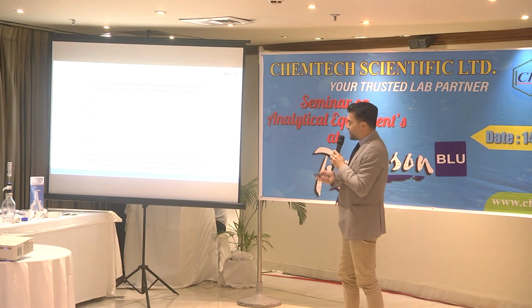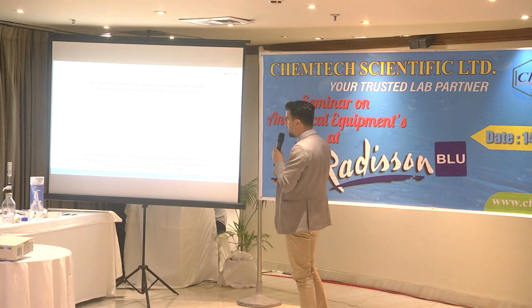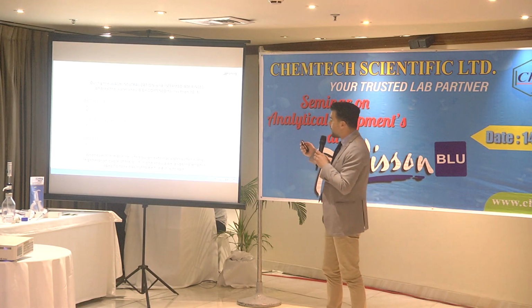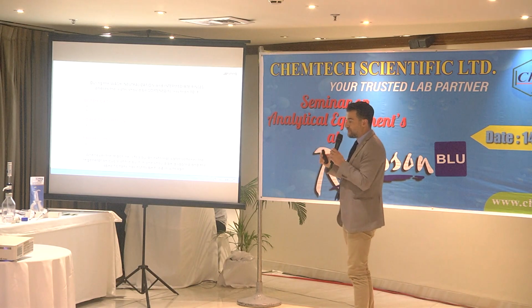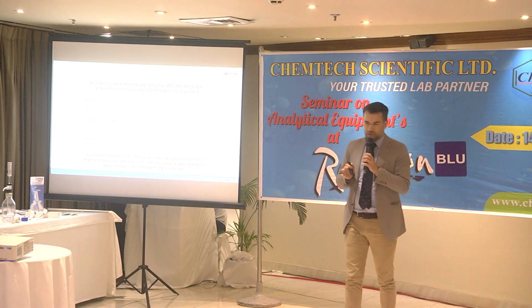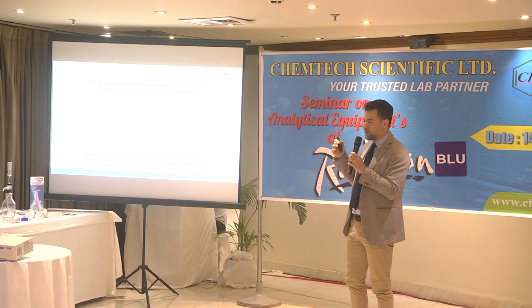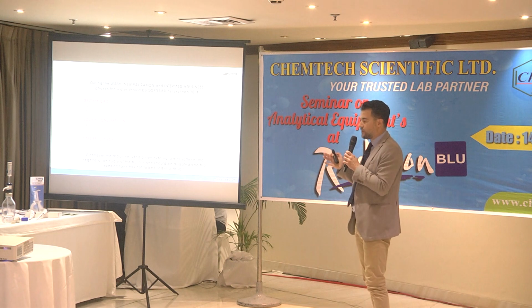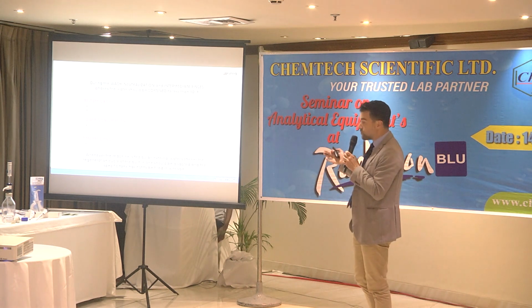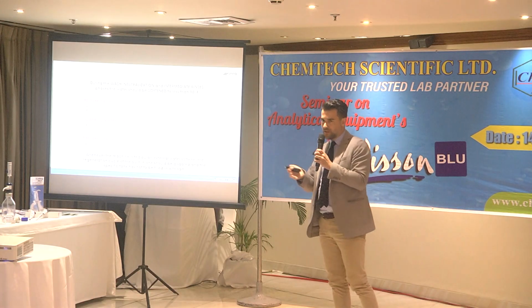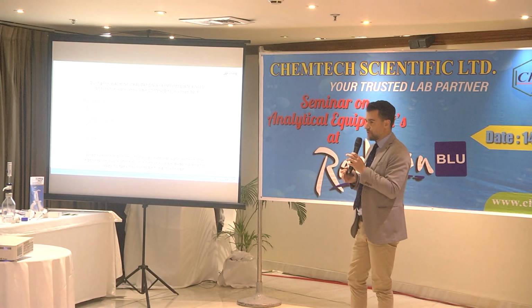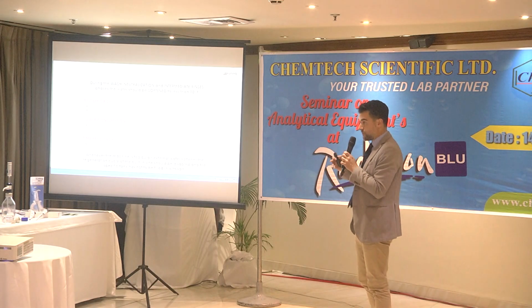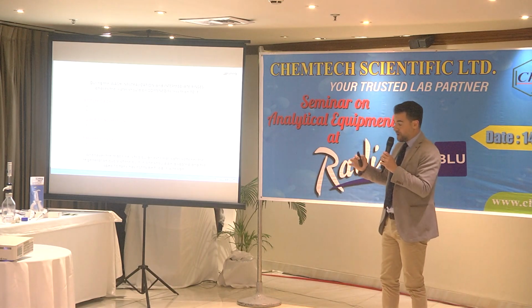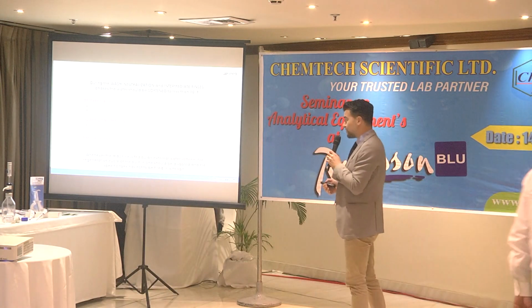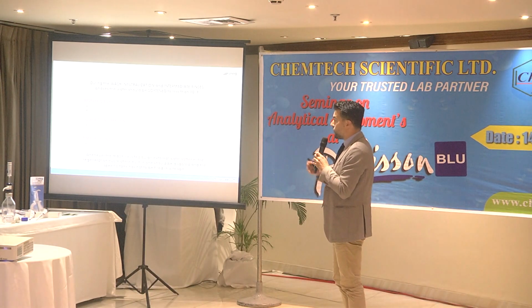This is an introduction picture, but the final rinse phase of the glassware washer must be done with neutral demineralized water. This is to avoid any residue on the glassware. You can decide to do all the cycles with demineralized water. This means that you need to have this kind of connection in your laboratory. If this connection is not available, we can also supply a purifier system that can produce demineralized water through osmosis.